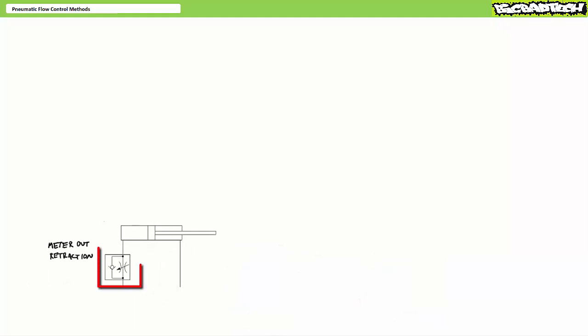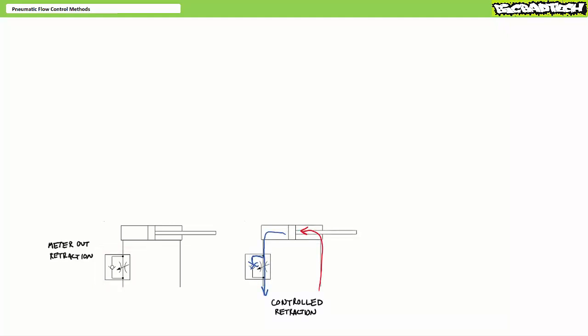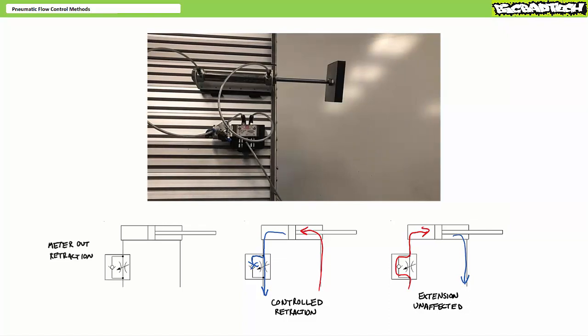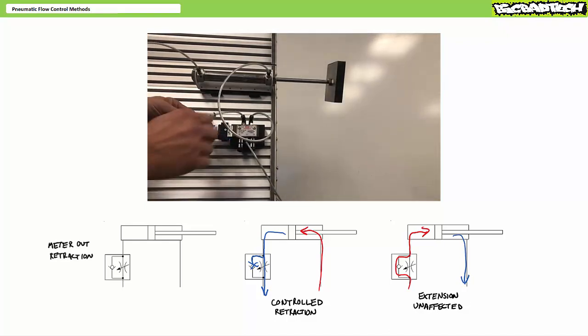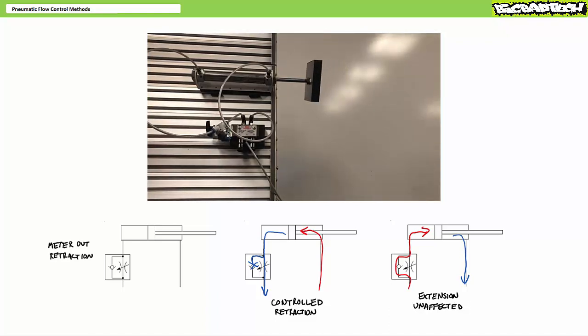Finally, let's take a look at meter out retraction. A meter out retraction arrangement makes use of a flow control valve with check valve bypass installed in the cap end, oriented in the following fashion. During retraction, air exhausted from the cap end forces the check valve poppet to the seat and all flow must travel through the narrow restriction orifice. Closing the orifice backs up air in the cap end, thus slowing retraction speed. The check valve bypass allows the cylinder to extend at full speed — during extension, air entering the cap end pushes the check valve poppet off its seat since flow is unimpeded. With the flow control valve relatively wide open, the cylinder slams back. A couple more turns narrow the restriction orifice even more and the cylinder retracts a little bit slower. After a bit of fiddling, the technician can dial retraction speed into the desired range. Extension speed remains unaffected since the check valve bypass ensures air entering the cap end during extension is unimpeded.